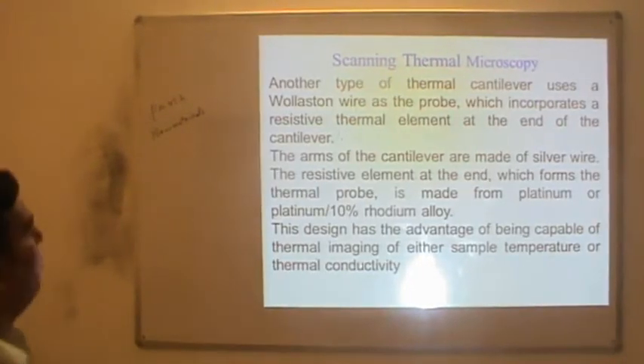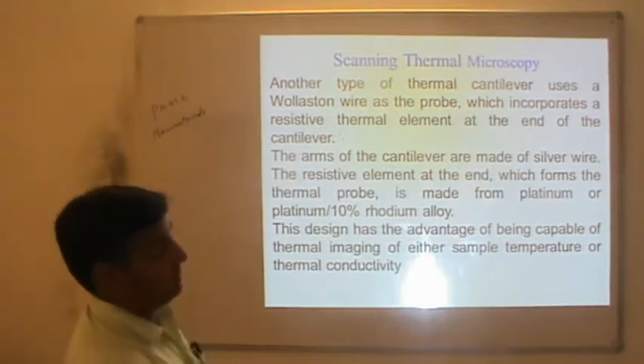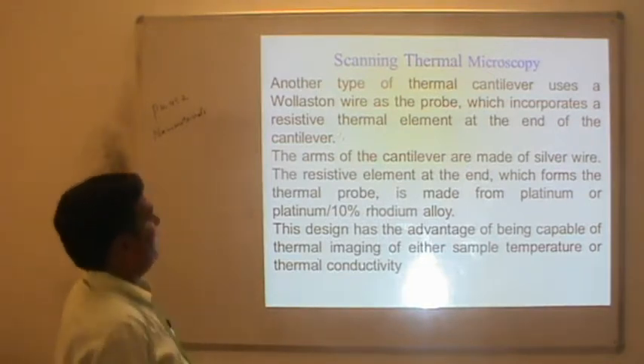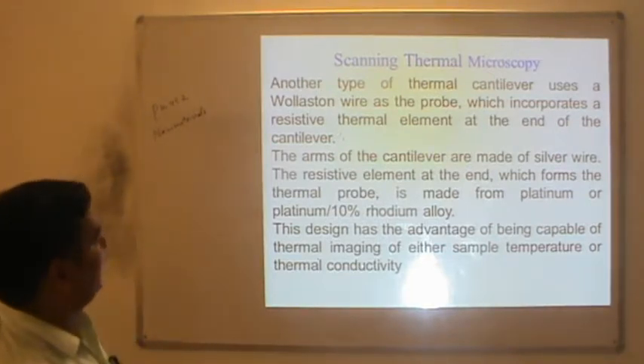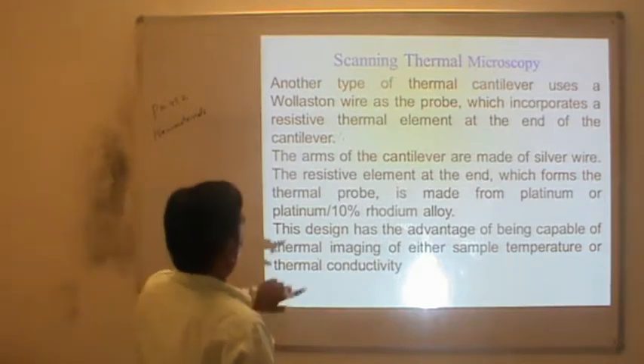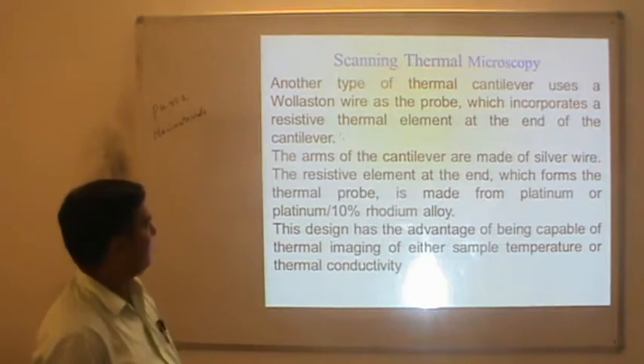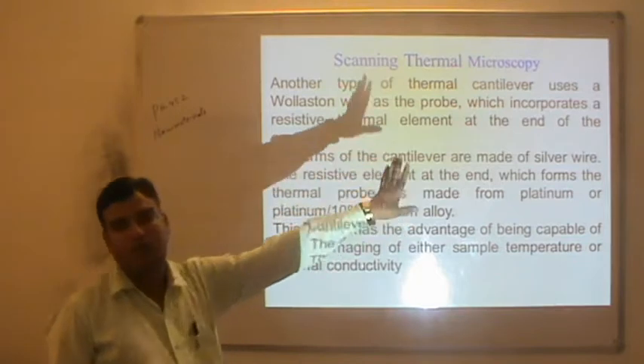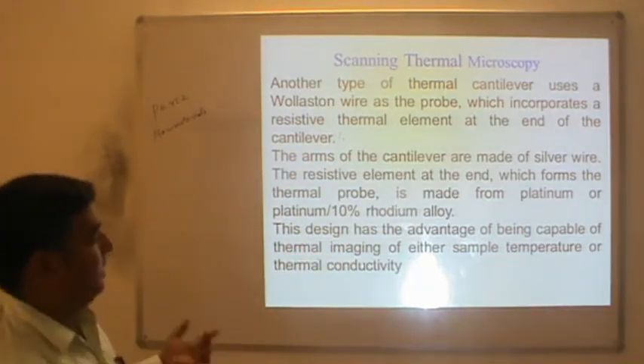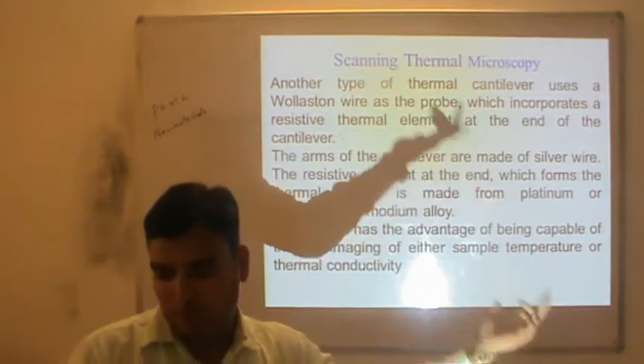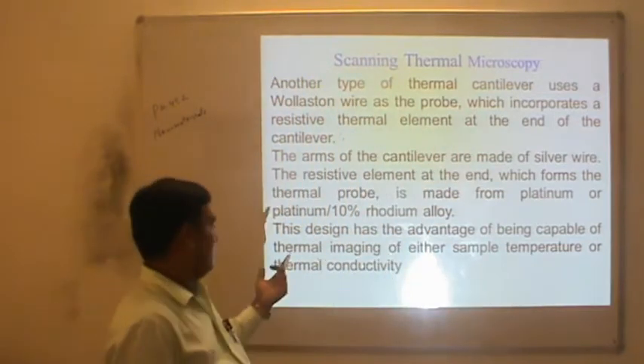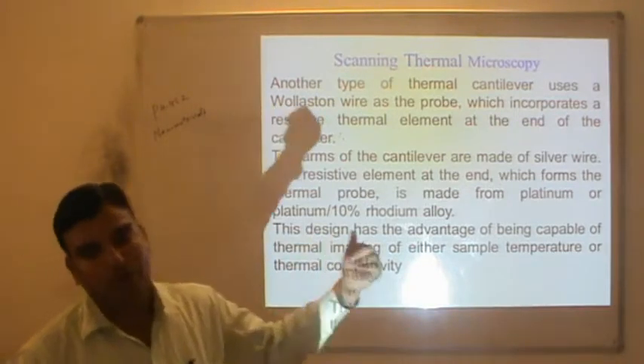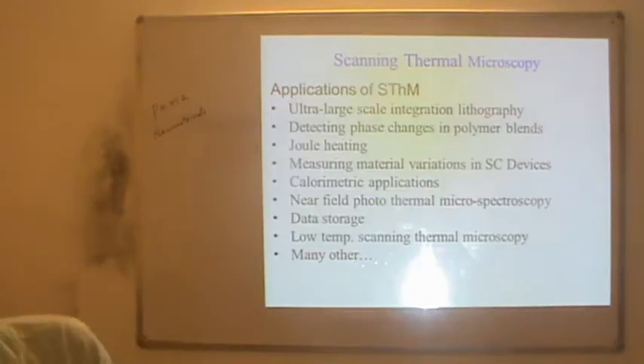Another type of thermal probe used in scanning thermal microscopy uses a Wollaston wire as the probe, which incorporates a resistive thermal element at the end of the cantilever. The arms of the cantilever are made up of silver wire, and the resistive element at the end — which forms the thermal probe — is made from platinum or platinum-10% rhodium alloy. Various alloys are also possible to use.